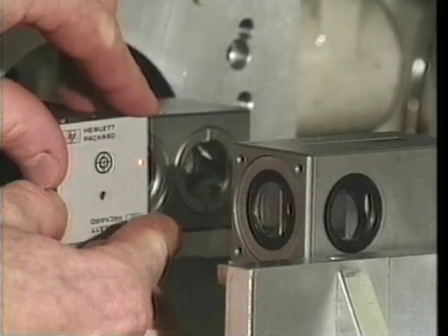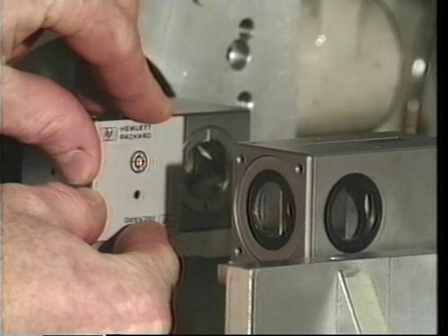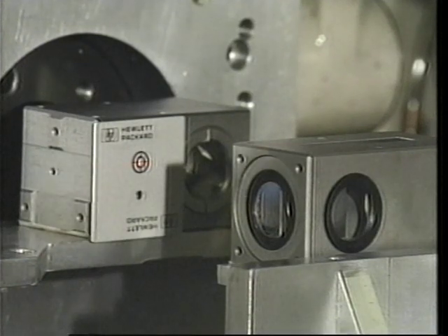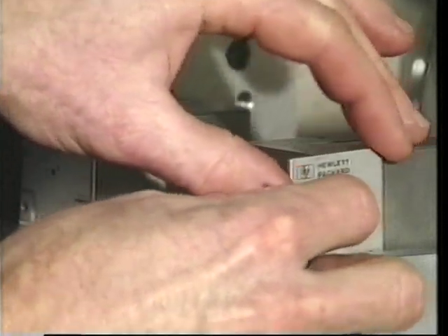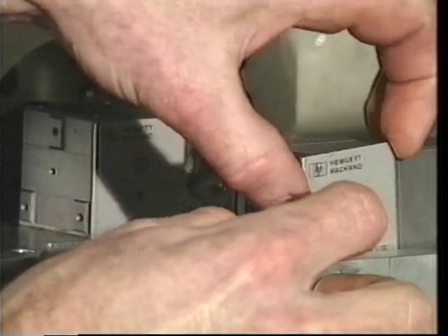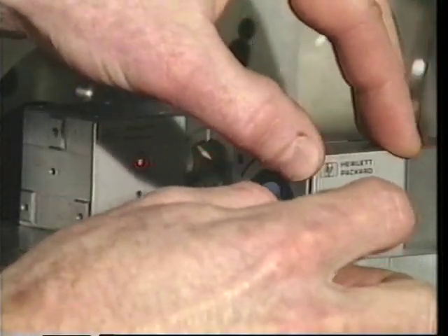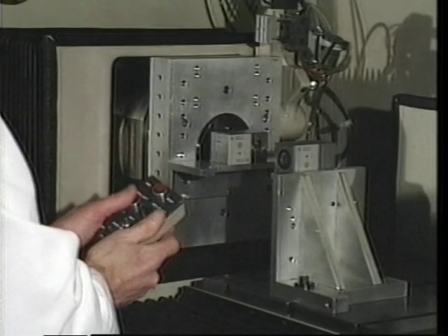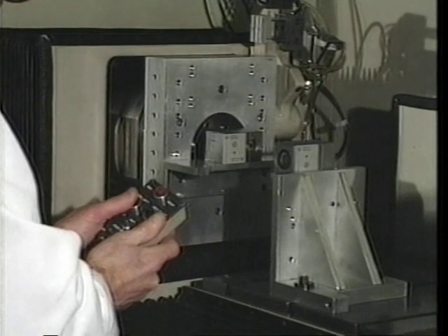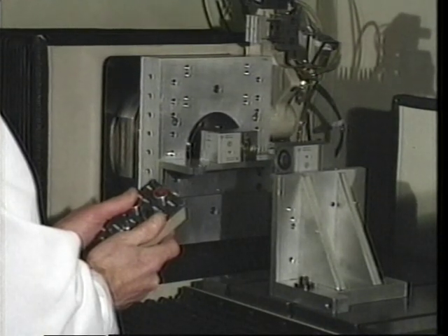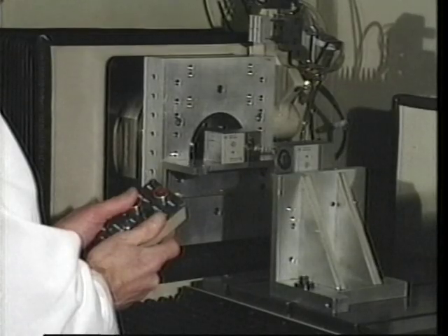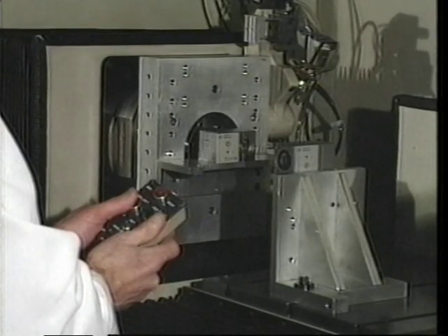To align the laser beam with the axis of travel, a target is placed on one of the retroreflectors of the angular reflector. The target is positioned so that its crosshairs are centered on the laser beam. Another target is placed on the entry-exit port of the angular interferometer such that its hole is centered around the laser beam. The reflector is moved away from the interferometer by jogging the z-axis slide in the positive direction. Observe that the red laser beam spot has moved away from the center of the crosshairs on the reflector target. When the spot has nearly moved off the target, jogging is stopped.